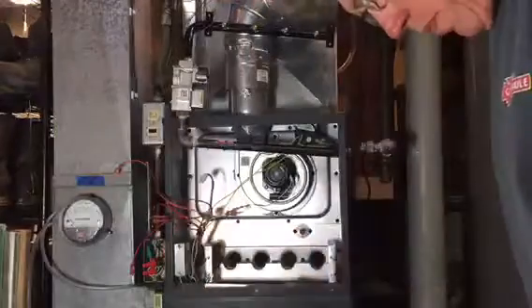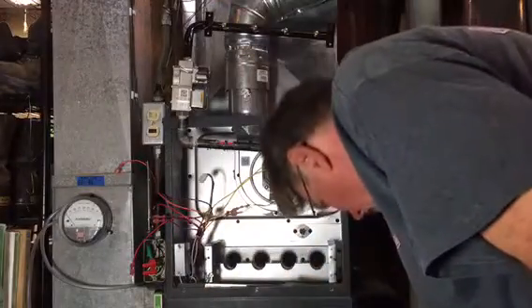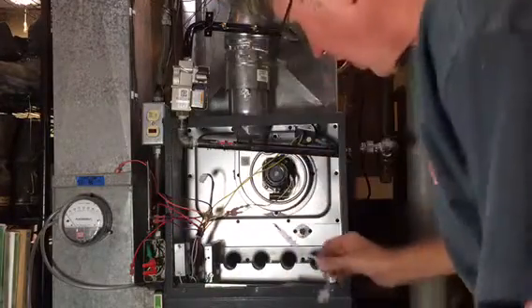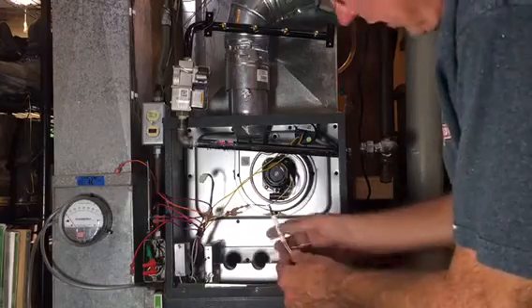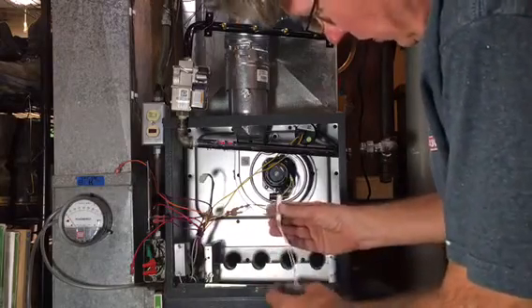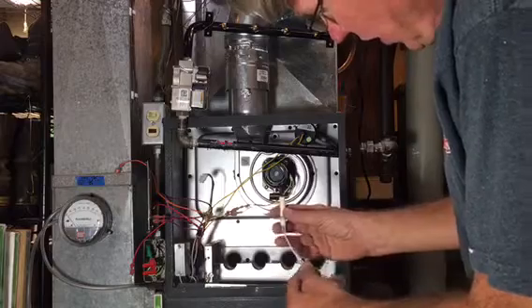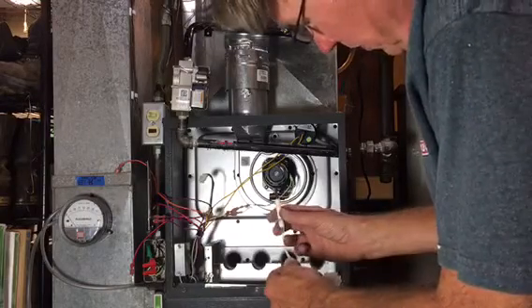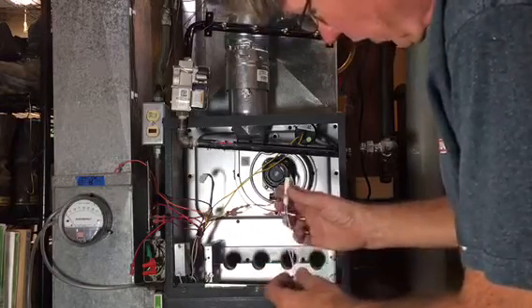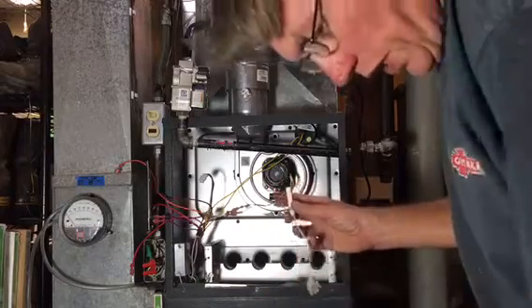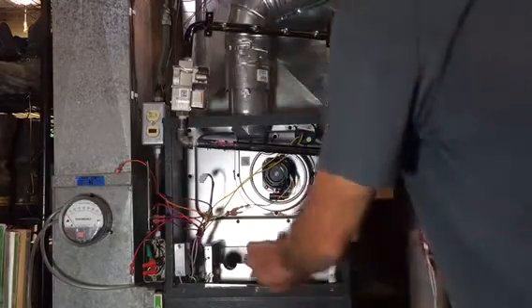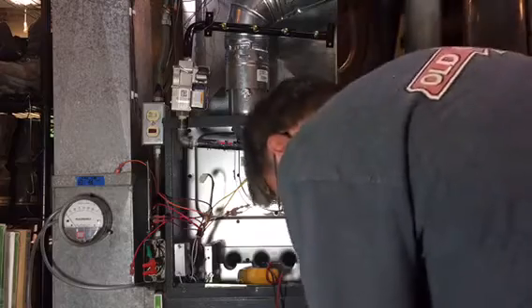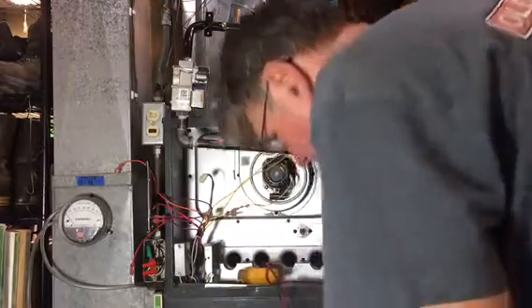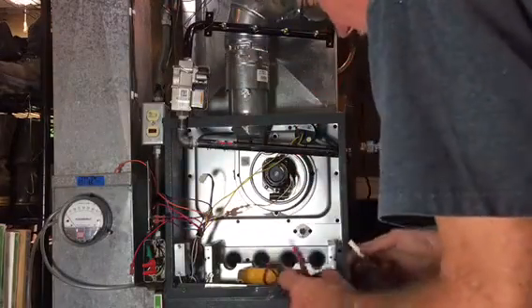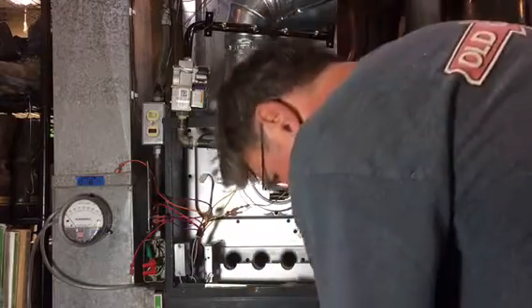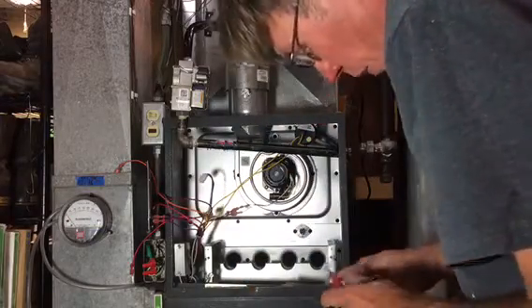Get right up. Okay, I mentioned a couple small devices. One is the igniter. This thing glows red hot when it gets the command from the circuit board, and that's what ignites the gas. Sometimes these fail. They don't last forever. They get really hot. They're not on very long. One quick test is to measure the DC resistance using a multimeter, and it should be less than 75 ohms. If it's higher than that, you might consider replacing it.